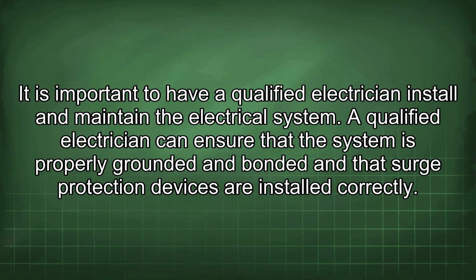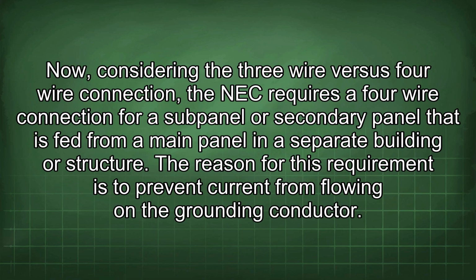It is important to have a qualified electrician install and maintain the electrical system. A qualified electrician can ensure that the system is properly grounded and bonded and that surge protection devices are installed correctly. Now, considering the 3-wire versus 4-wire connection, the NEC requires a 4-wire connection for a subpanel or secondary panel that is fed from a main panel in a separate building or structure.